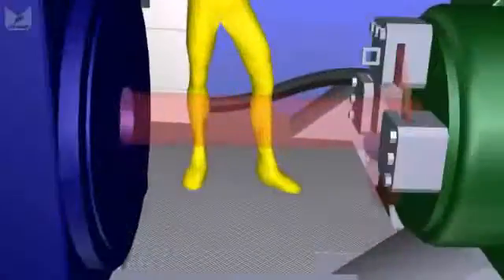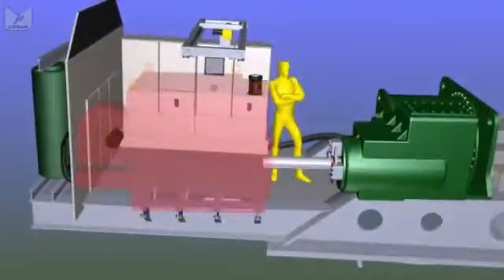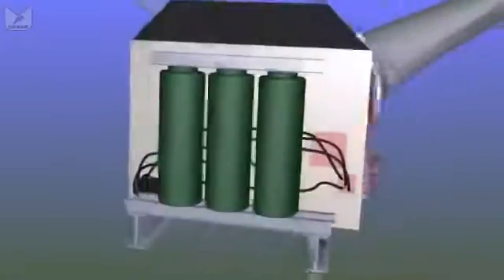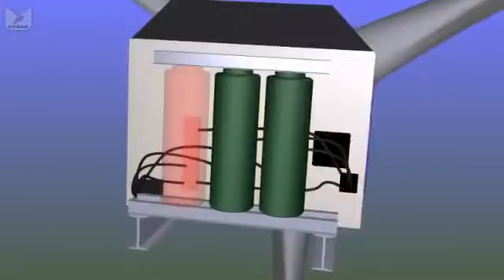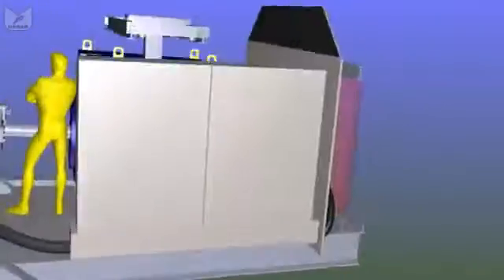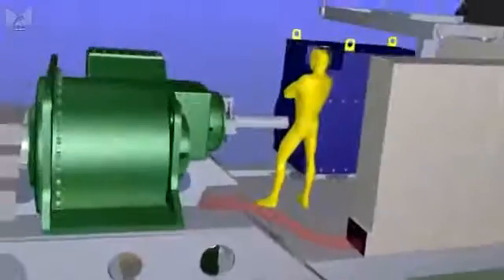Out of the back comes a high speed shaft - that's where the braking system is. The high speed shaft then drives the generator, which is usually oil filled. The generator then supplies 690 volts in this case into our transformer which is sitting right next to it. That high voltage signal then passes through the switch gear and the cabinet, down the dropper cable straight down to the bottom of the tower through those switches on platform two and off to the substation.